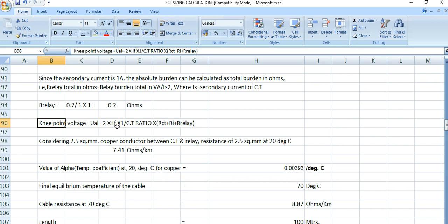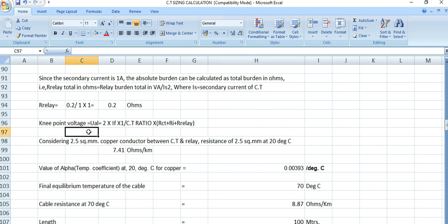The knee point voltage formula is given by: twice into IF — IF is the fault current which is 40 kilo ampere — multiplied by 1 divided by the CT ratio (which is 1000/1 ampere), multiplied by R_CT plus R_I plus R_relay, where R_CT is the CT resistance, R_I is the lead resistance, and R_relay is the relay resistance.